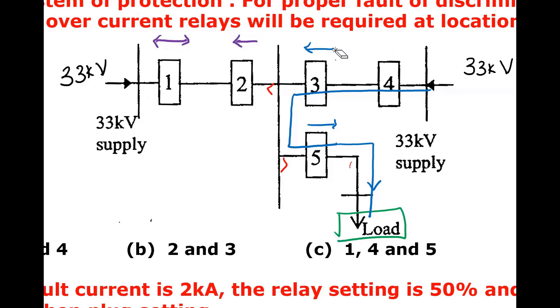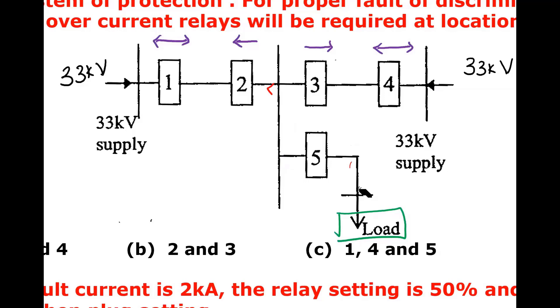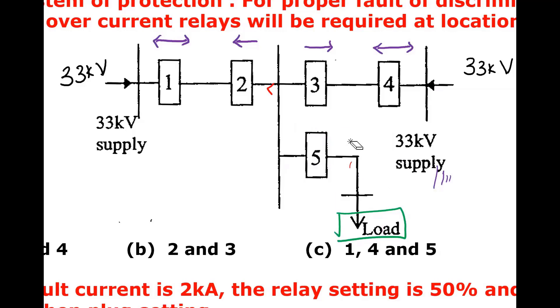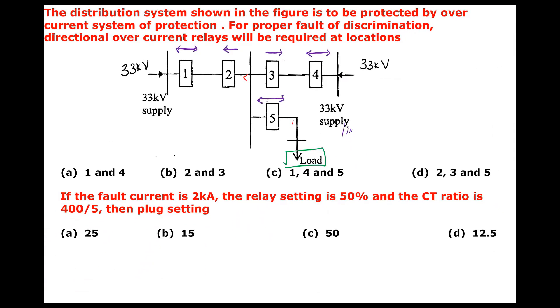Similarly, carrying out the same exercise for relays 3 and 4: relay 4 is non-directional and relay 3 is directional. For relay 5, since both normal and fault current directions are the same in its zone from the relay location to the load, relay 5 is non-directional. Therefore, only relays 2 and 3 are directional relays.